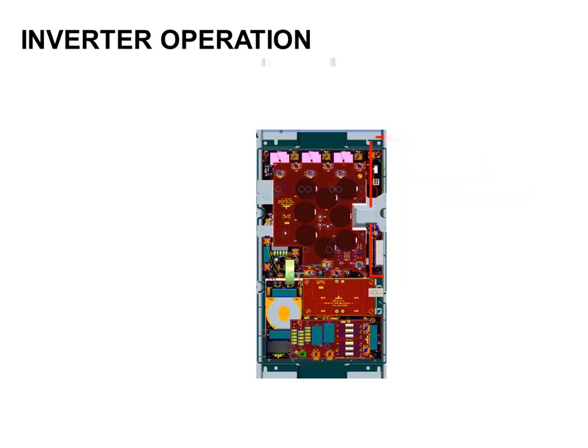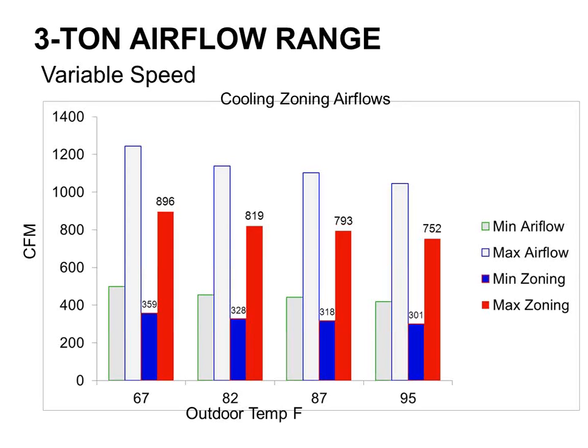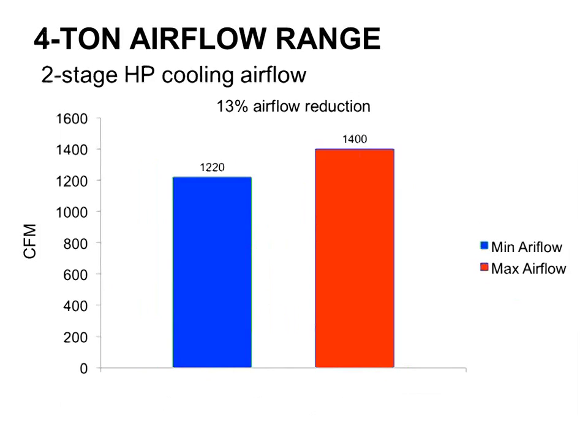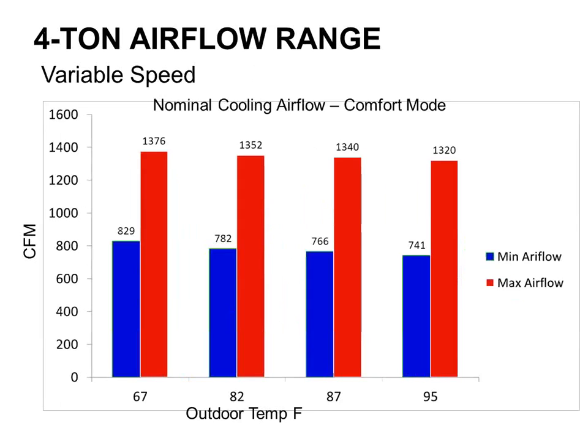If I want to put zoning systems on there, having variable capacity cooling and variable capacity heating is kind of a no-brainer if I want to be able to have one or two zones calling for cooling or heating by themselves. So bigger turn downs on zoning systems is a plus. That's a 4-ton example. It's the same thing. I don't need to do that one.